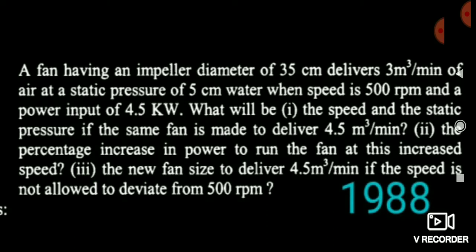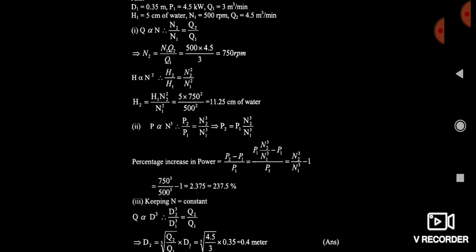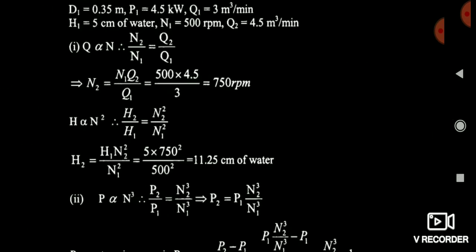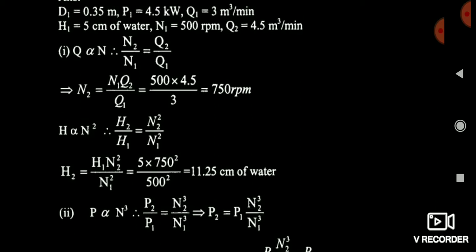Another question asked in 1988 looks very lengthy and difficult, but it is actually very easy. The impeller diameter is 35 cm and delivers 3 m³/min of air at a static pressure of 5 cm of water, with a speed of 500 RPM and power input of 4.5 kW. The same fan is made to deliver 4.5 m³/min. Q2 is 4.5 m³/min and Q1 is 3 m³/min. Using the linear relationship N2/N1 = Q2/Q1, we calculate N2 = 750 RPM.